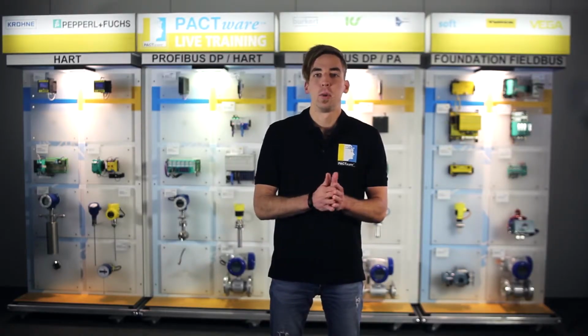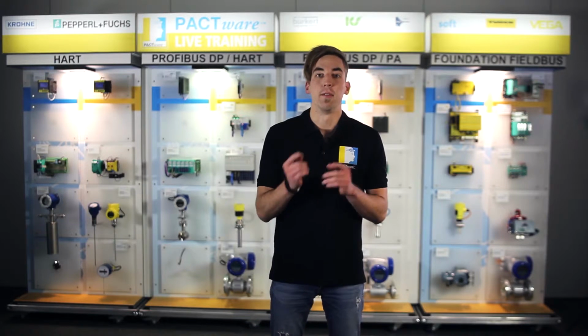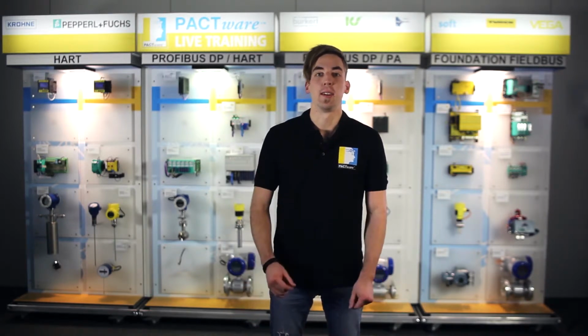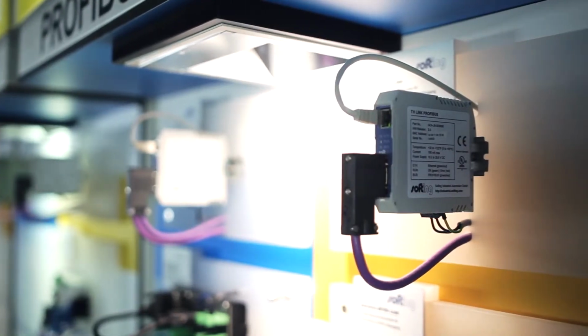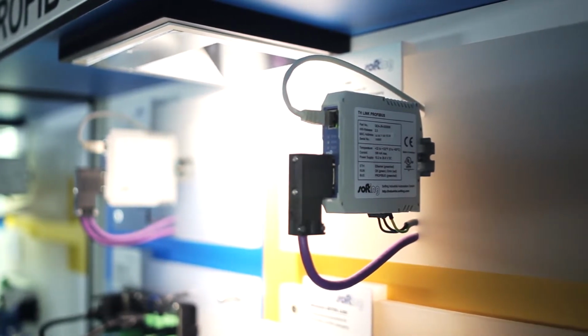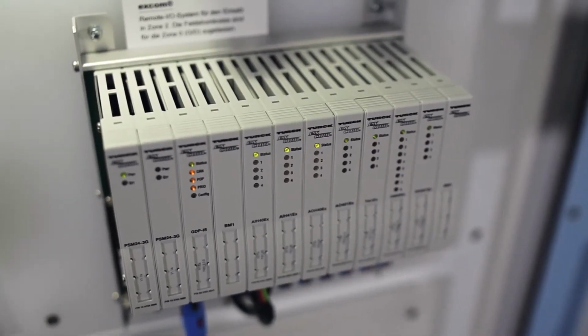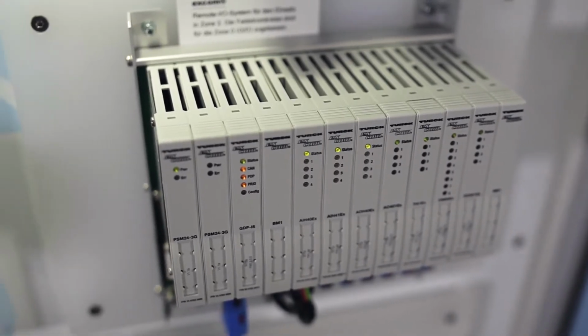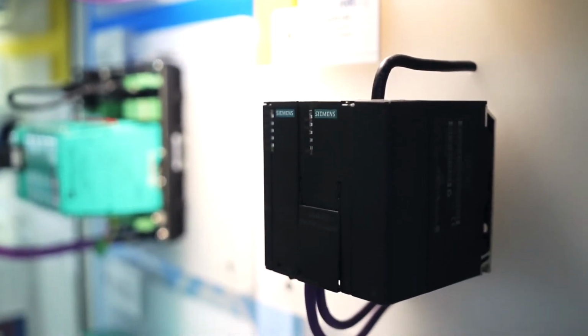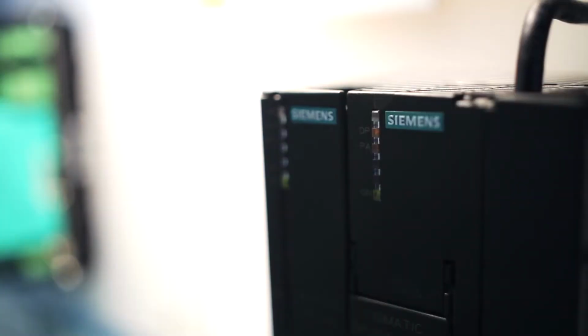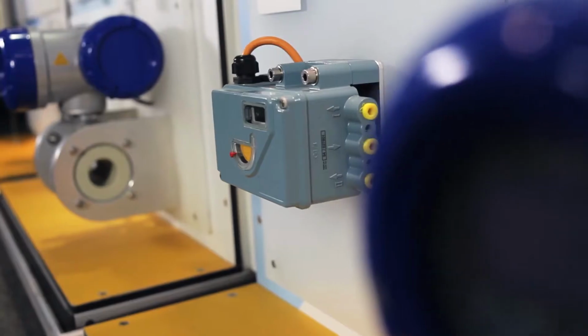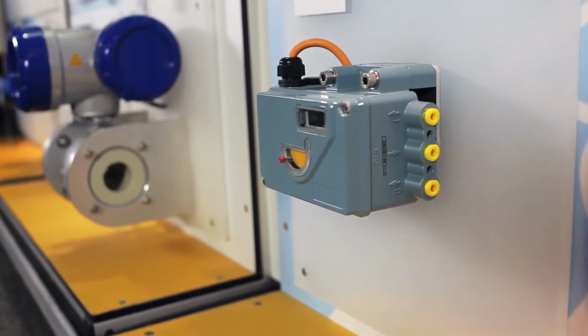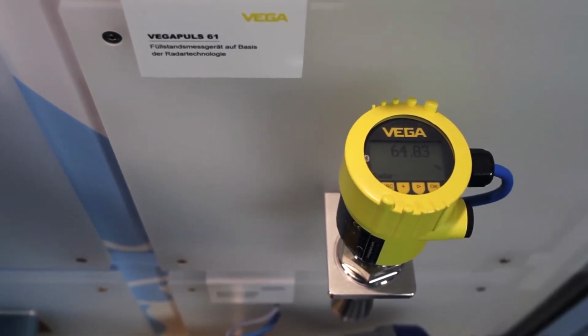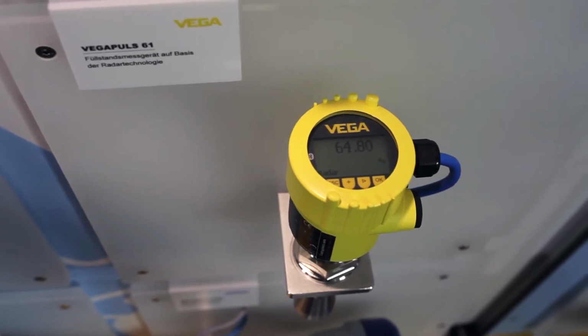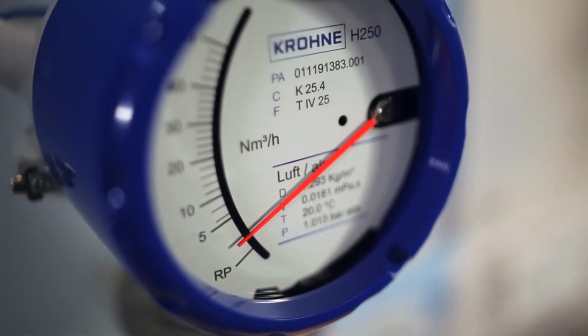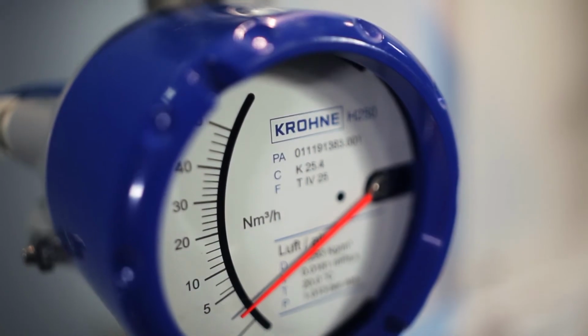Basically, we can distinguish between two different types of DTMs, the device DTMs and the communication DTMs. Communication DTMs are being used by infrastructure components such as gateways, remote I/Os, or segment couplers. Those devices are made to just forward information and data through various communication layers and bus systems. Device DTMs provide a comprehensive functionality around the field devices being used. This includes parameterization, configuration, documentation, and diagnosis of those devices.